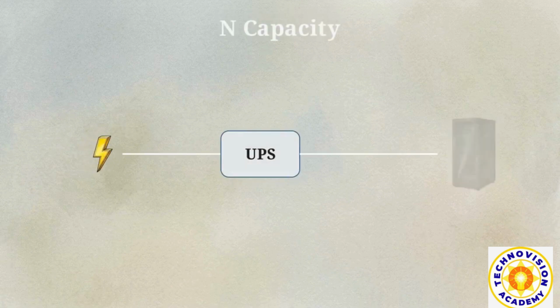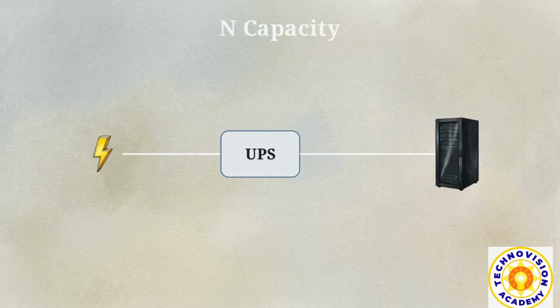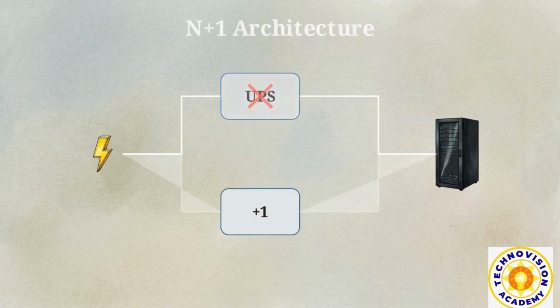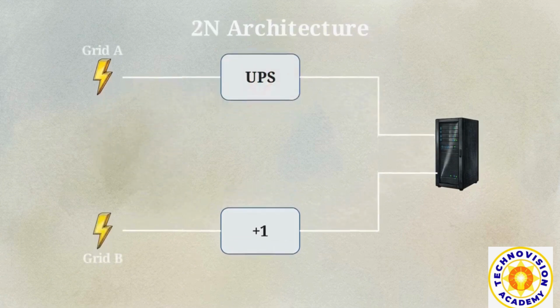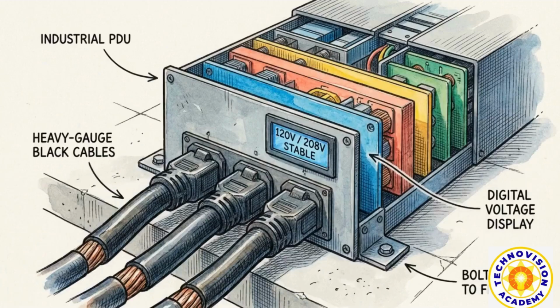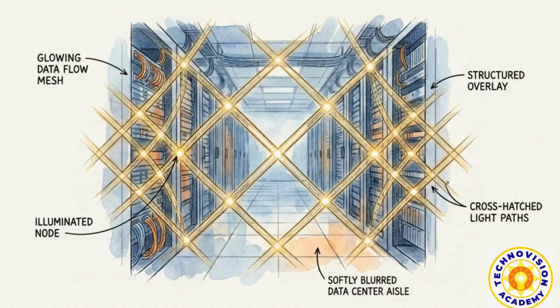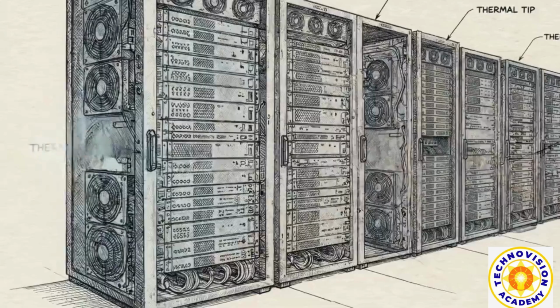This outlines redundancy. An N architecture is the minimum equipment capacity, like a single UPS, needed for the server load. Adding a backup creates N+1, rerouting power if the primary fails. 2N duplicates everything. Mirrored pathways eliminate any single point of failure. Downstream, automatic transfer switches and power distribution units instantly route this cleaned, redundant energy directly into the server racks without requiring any human intervention. Engineers achieve continuous uptime by mathematically layering overlapping pathways of failure recovery into every stage of the power chain.